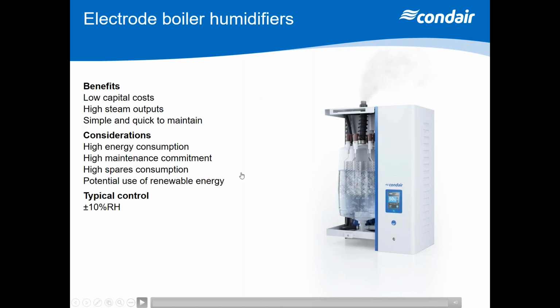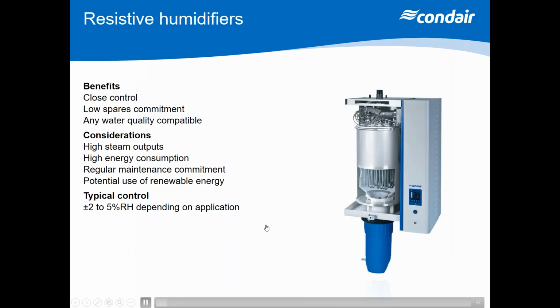So we've got to change those cylinders. Again, could be £400, £500, £600, depending on the size of the cylinder. But because it's using electricity, we do have the potential for the use of renewable energy. So the critical thing to remember is what's my water quality and what's my control requirement. Now, if this doesn't meet your requirements, then you would go to a resistive heater humidifier. Capital cost has just gone up by about 2.5 times to go for a resistive heater, but it's a different beast. It's a different machine completely.